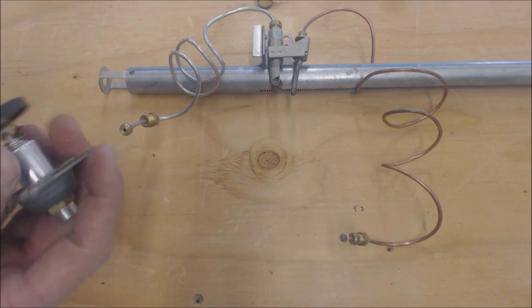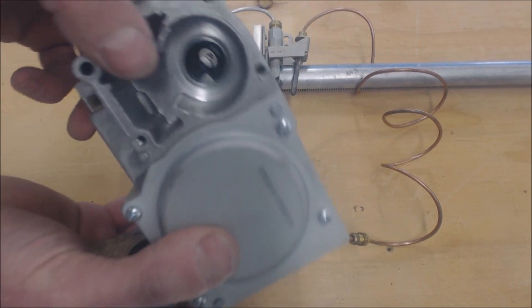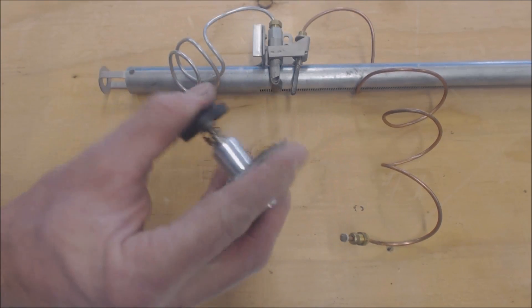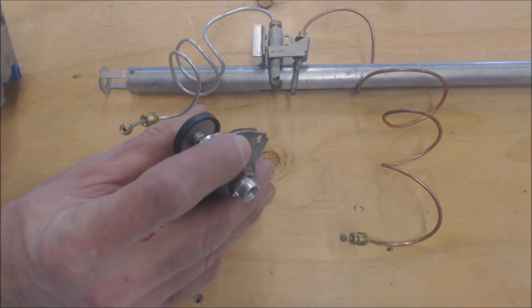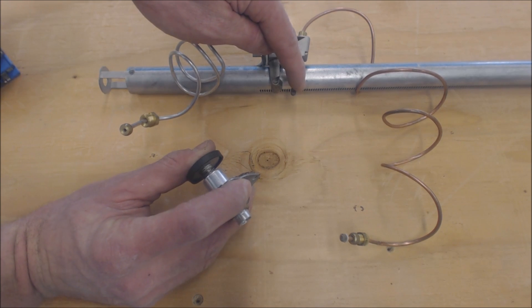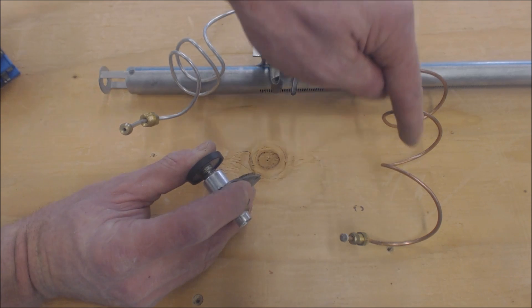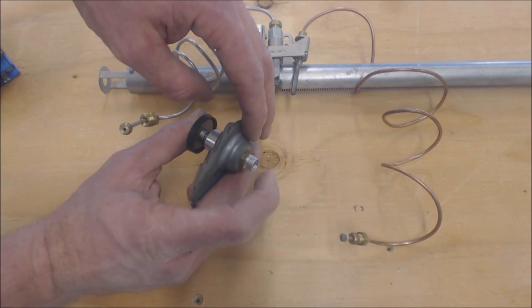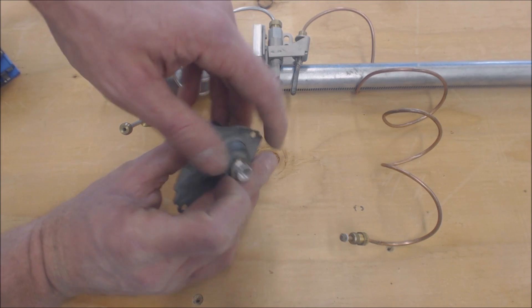When you heat a thermocouple rod up, it actually sends DC millivolts through right over to here and into the back of the solenoid. The solenoid has two connections, straight down in the middle and the side, and the thermocouple has two wires as well.